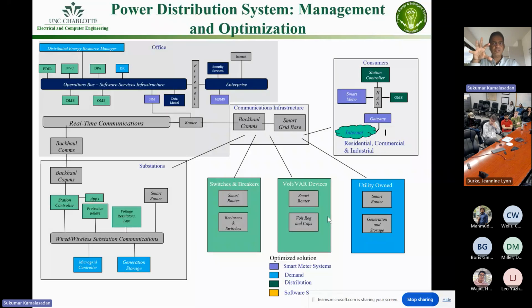Looking at feasible ways of managing grid assets including IBRs, the idea is that each utility area should have at least one or two assets that we can manage, not necessarily a lot. Having many controllable assets is good but increases complexity, so the controllable asset should be few but managed by the utility, with flexibility to control several inverter-based resources or distributed energy resources in the field.